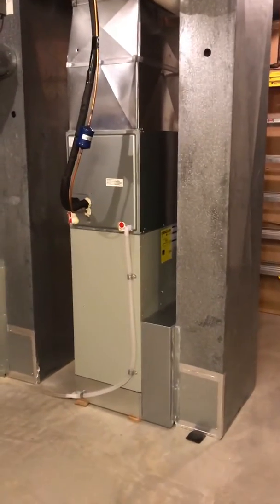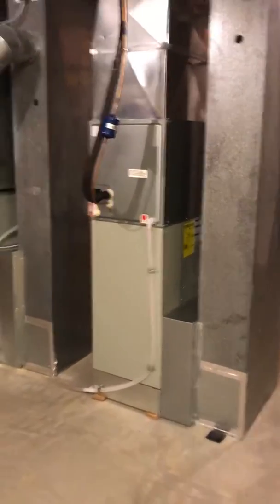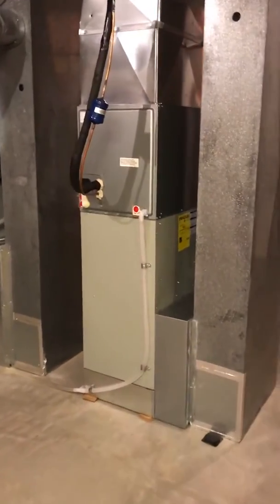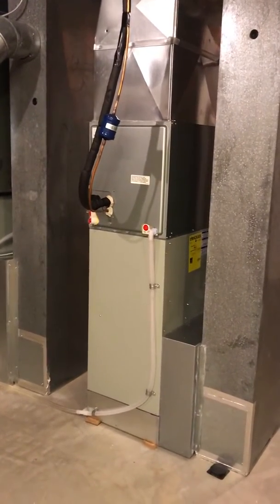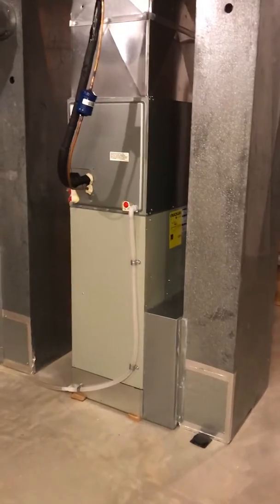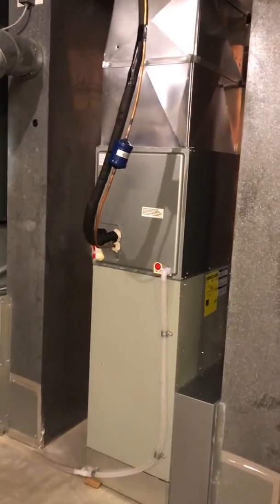Rick at Christie's basement — we're going to be updating the AC unit and installing an A-coil on top of the S9V2 that we just installed. Looking at the backside, the good news is we'll be able to get that A-coil out from the back. I'll pop around the front — we won't have to cut any of the new piping.